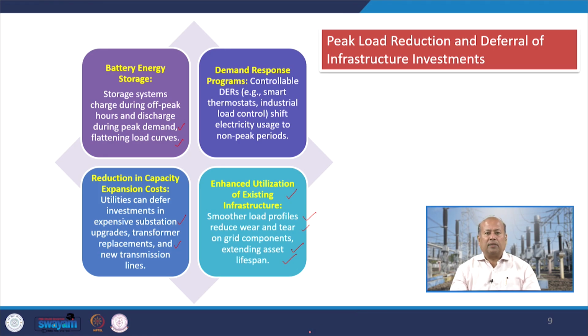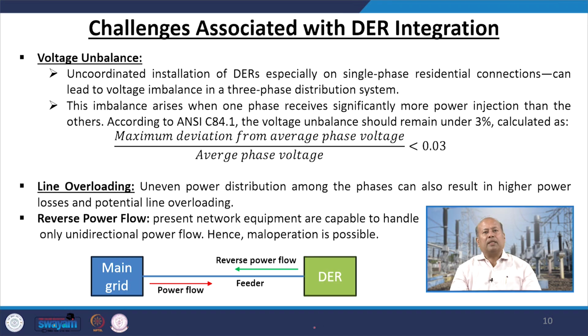What are the challenges? We have all discussed the benefits as of now. Now, the challenges associated with DER integration, the first one is voltage unbalance. That is, uncoordinated installation of DERs, especially on single phase residential connections, can lead to voltage imbalance in a three-phase distribution system. This imbalance arises when one phase receives significantly more power injection than the other.